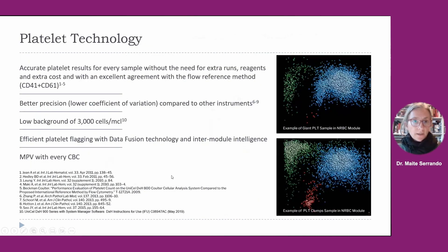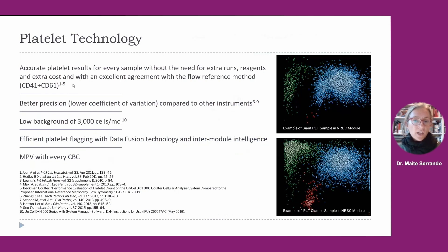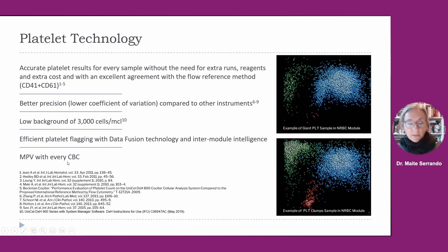To finish the technology introduction, for platelet technology we highlight that we have accurate platelet results for every single sample without the need for extra channels or reruns. We have better precision compared to other instruments, with a low background for cases with severe thrombocytopenia, and efficient platelet flagging with Data Fusion technology and inter-module intelligence. MPV results are also available with every single CBC measurement.